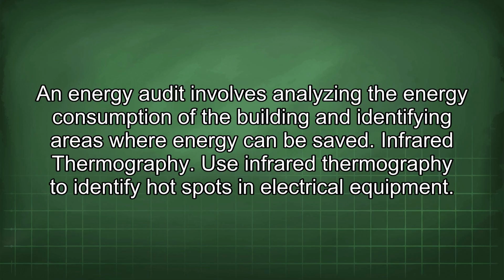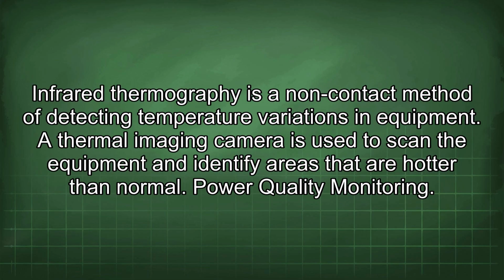Infrared thermography. Use infrared thermography to identify hot spots in electrical equipment. Infrared thermography is a non-contact method of detecting temperature variations in equipment. A thermal imaging camera is used to scan the equipment and identify areas that are hotter than normal.